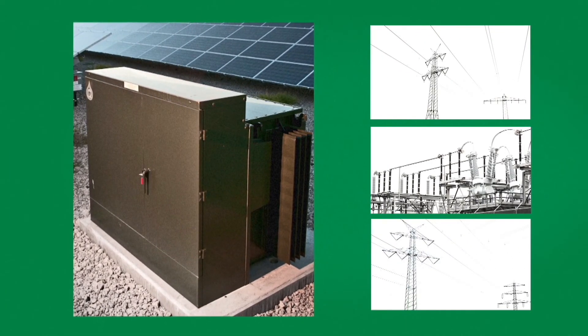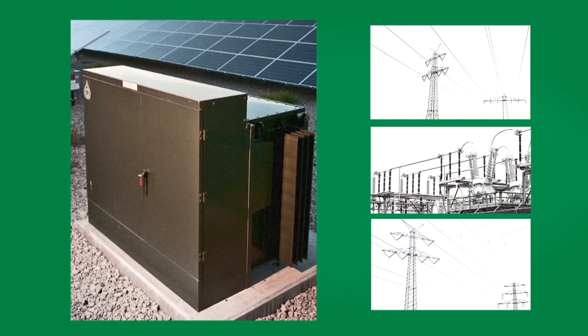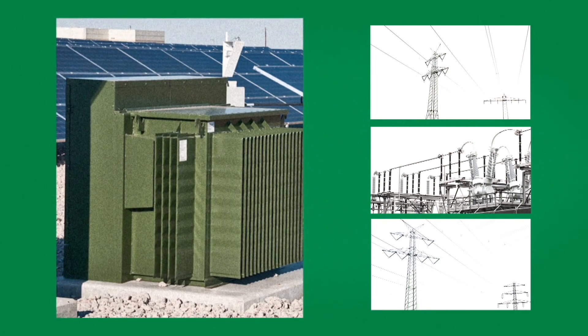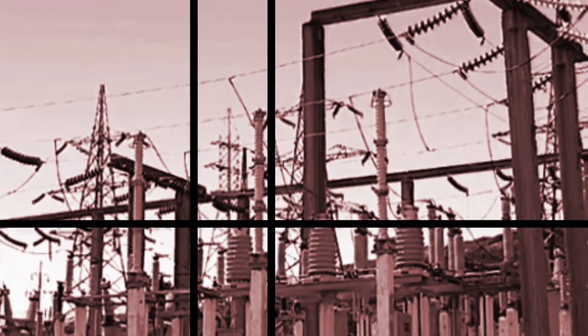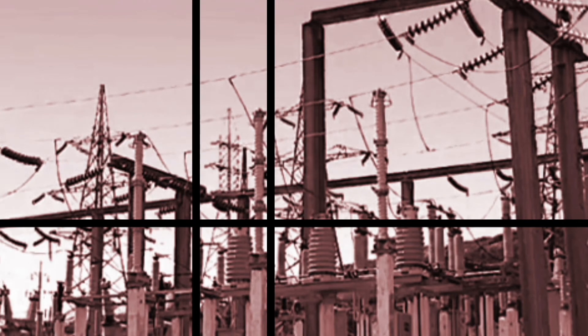The second step is, how do we make that substation where we don't have to put in dike systems, firewalls, or concrete containment for spills? Then you start talking about total cost of ownership, where a natural ester solution is probably much less expensive than a mineral solution.